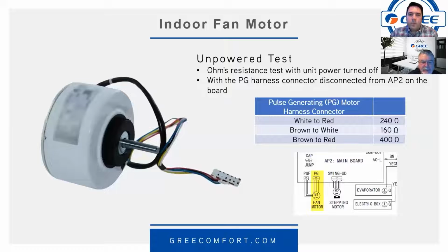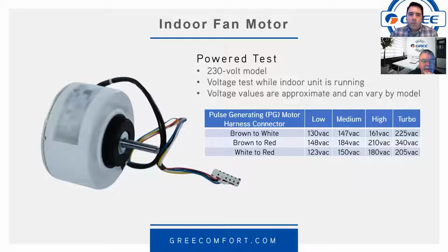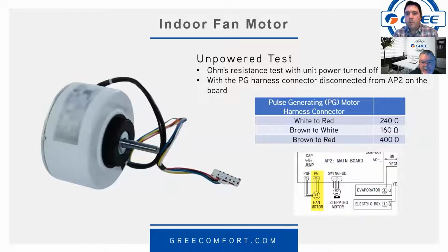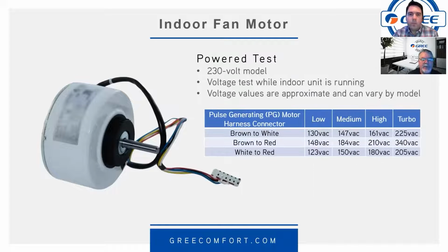And sometimes, and I should mention this because they show it in there as the PG motor, PG fan motor, right? And that's a pulse generating is what the PG stands for. Pulse generating motor is your indoor fan. So the powered test, this 230 volt model, while the indoor unit is running, you can check brown to white, and on the different speeds, you should see these different settings. Obviously, if you go to turbo, then you know what speed it's running at.